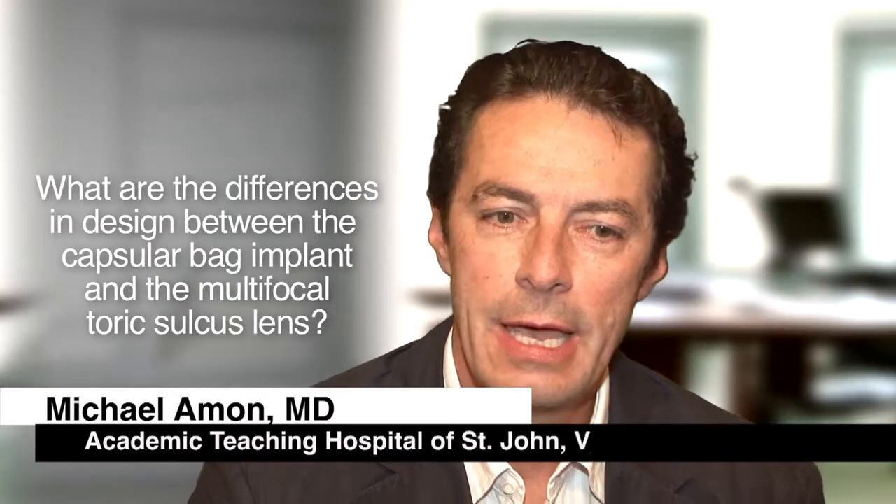The difference in design is that the sulcus lens has to have a larger diameter. The sulcoflex lens has a 14mm diameter as compared to the smaller diameter of a capsular bag lens. Another feature is that there is an undulation in the haptic, because we want to have high rotational stability. The haptics of the sulcoflex lens are undulated. Another important thing is that the posterior surface of the optic of the sulcoflex lens is concave.